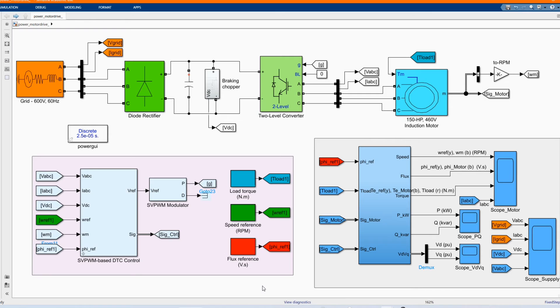In this video, we are going to show how to simulate a direct torque control with a space vector modulation of an induction motor. The idea of the system is electrical energy supplied by a three-phase AC to DC diode rectifier connected to a grid of 600 volts. The DC bus is connected to a three-phase two-level converter, which generates the variable voltage and frequency required for variable speed operation of an induction motor.